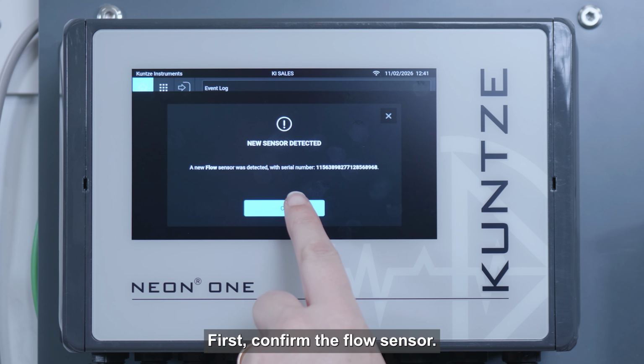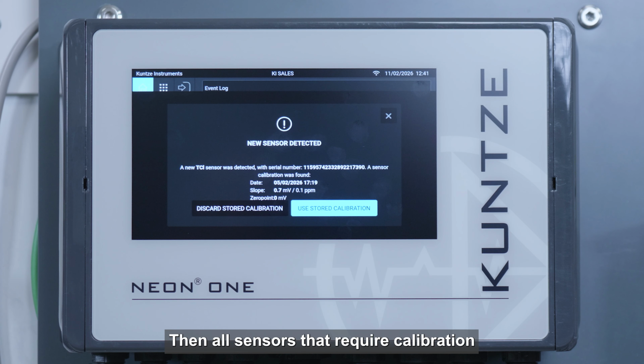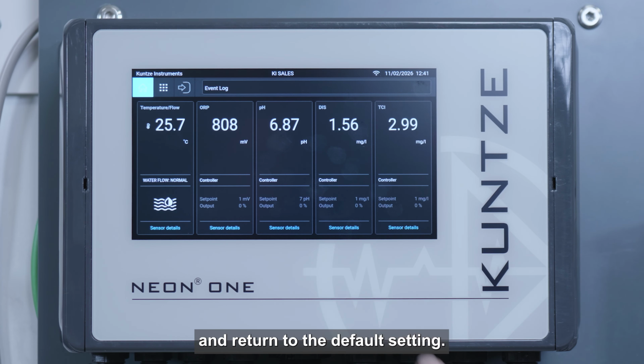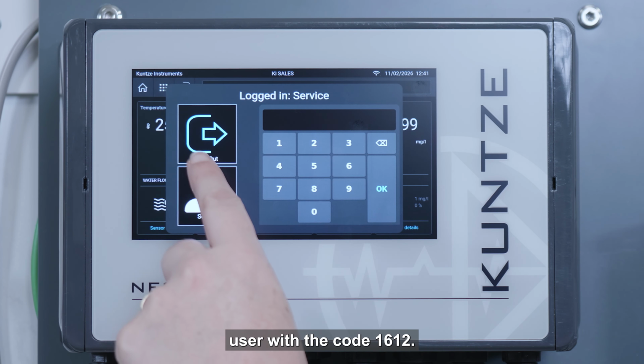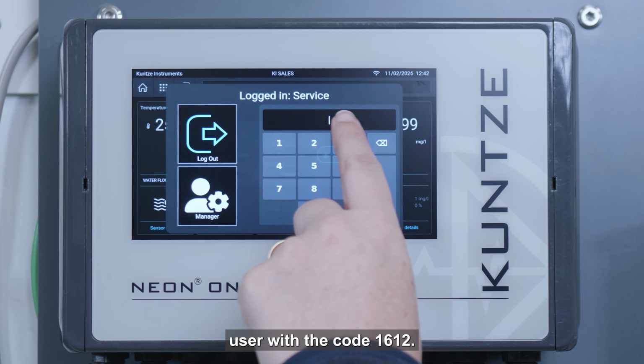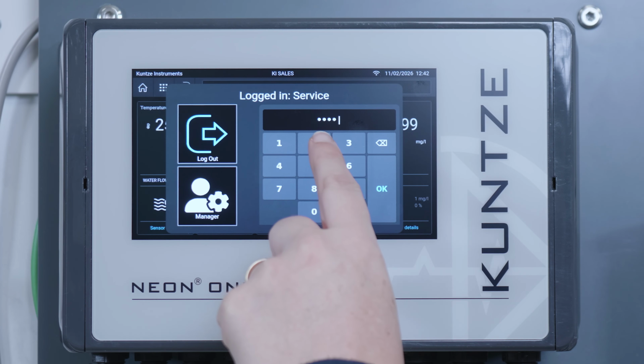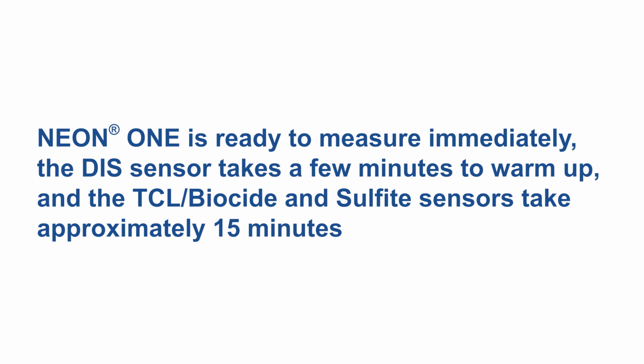First, confirm the flow sensor. Then, all sensors that require calibration will be queried as to whether the stored calibration should be used or whether you want to discard it and return to the default setting. Then return to the manager user with the code 1612. Neon One is ready to measure immediately.